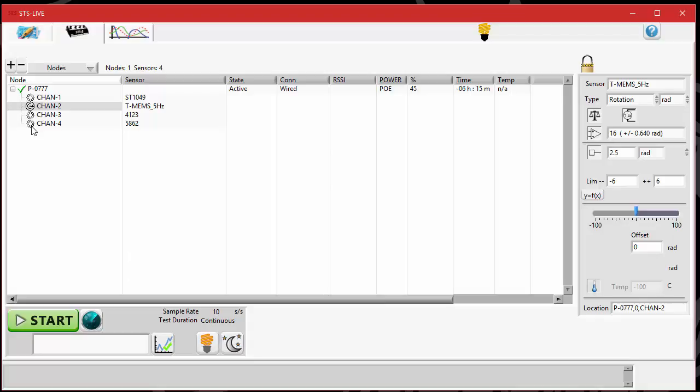If you ever get a question mark or a blank where there's no icon, it means that something happened when it was trying to load the calibration file and it wasn't able to detect that sensor correctly. So before you run a test, if that's the case where there's a question mark or a blank, you want to check out my other video on what to do for loading up calibration factors for gauges.